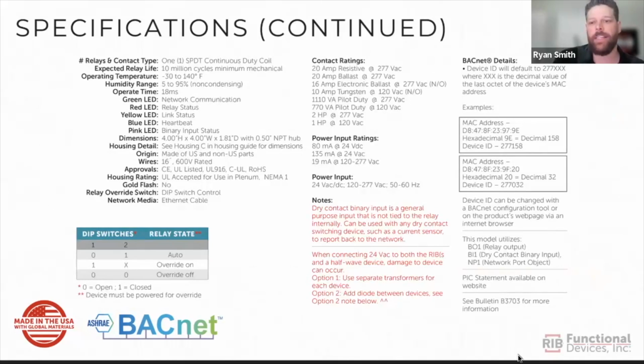This page has the rest of the specifications for the new relay. Some important things you'll want to note here is that the relay is rated for 20 amps. It must be continuously powered by 24 volts AC or DC, or with the 120 to 277 volts AC. This wide range of voltage makes it easier than ever to power the relay with a readily available power source on your project. There's also various LEDs on the top of the relay to indicate network status, relay status, and binary input status.